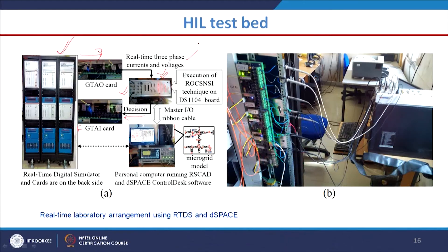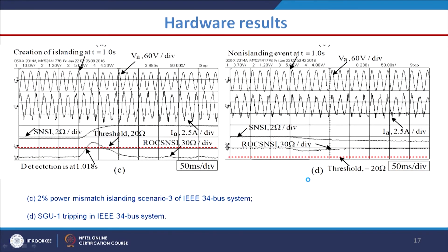Inside the dSPACE, the ROCSNSI algorithm is coded using MATLAB 2013A. The dSPACE receives the analog voltage and current signals, calculates the rate of change of superimposed negative sequence impedance, and sends the decision back to the RTDS via the GTAI card, where the circuit breaker of the DG is opened if islanding is detected. A sample hardware result shows the SNSI crossing the threshold, generating a trip signal.